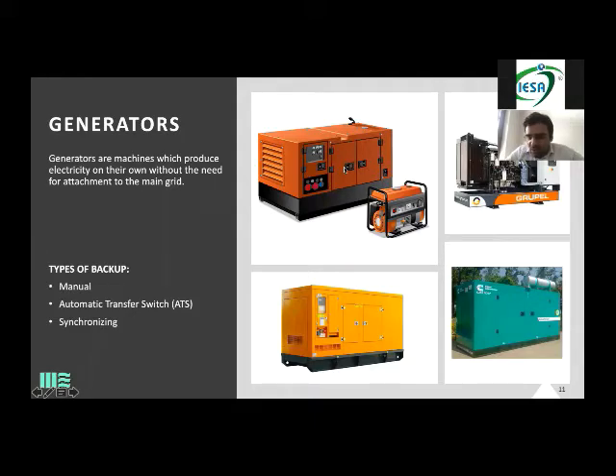Which genset gives maximum output, it doesn't depend on the company. You can have a Cummins, a Caterpillar, a Kirloskar on site. It just depends on the capacity of the genset. Normally the genset can give you 80% of load if it is maintained properly and in a healthy condition. If you're taking a 500 kVA genset, it means 400 kilowatts. The simple calculation anybody wants to do on site is that to convert kVA to kilowatt, you multiply it by 0.8. So 400 kilowatts is the 100% output.